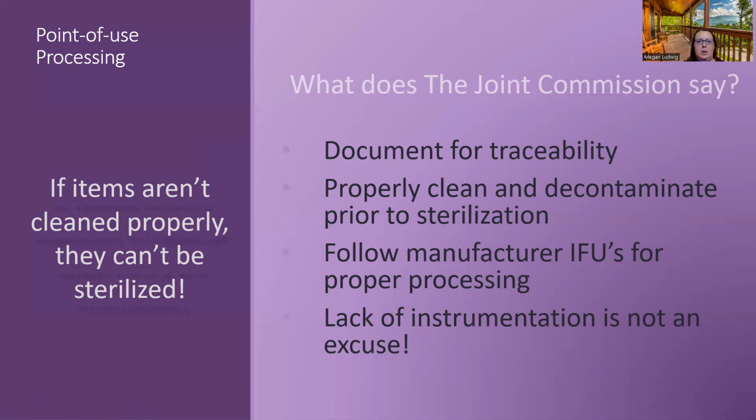If you have that bloody hemostat that you didn't rinse off and brush off all the blood and you just throw it in the sterilizer, it's still not going to be sterile. It has living tissue on it. Living tissue cannot be sterilized. That's important, okay? So we have to remove all that living tissue. That living tissue is called bioburden. We have to get rid of that before we sterilize it.